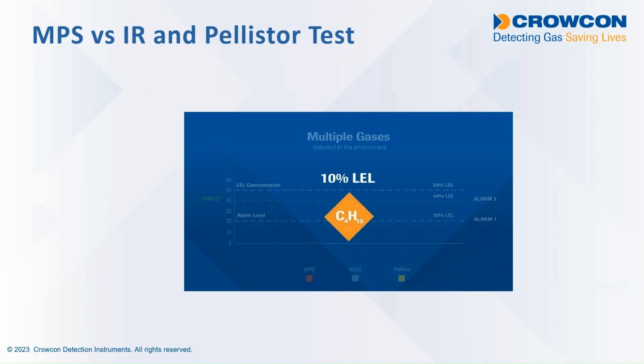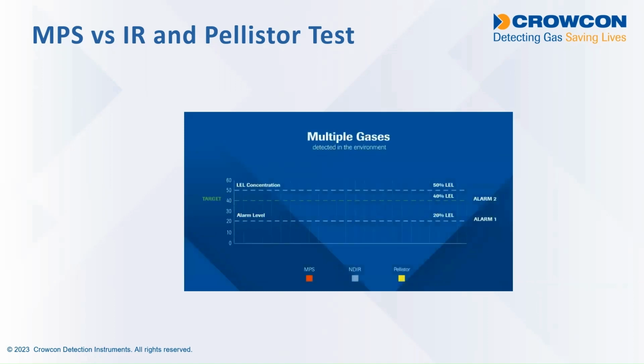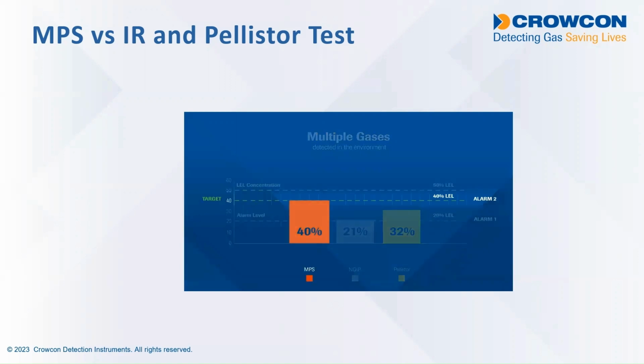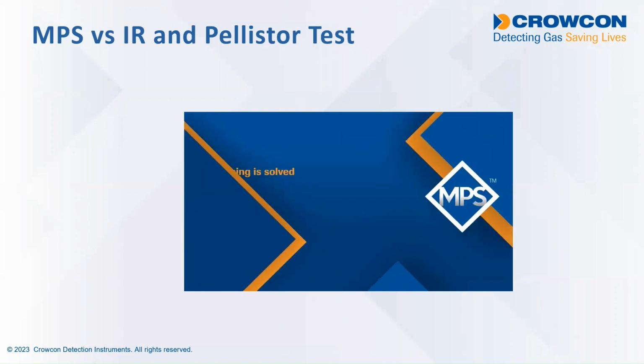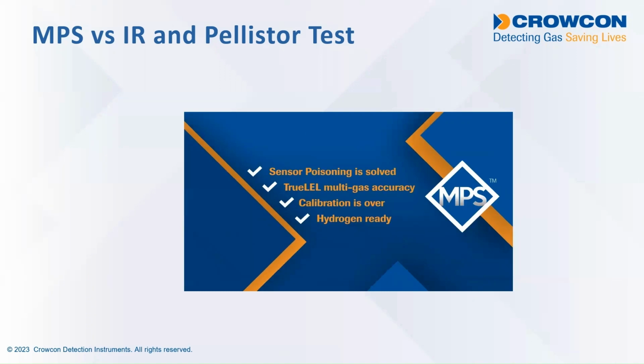And this is exposure to a mix of gases, so 50% LEL of methane, 20% LEL of hydrogen, and 10% LEL of butane. If you have a mixture of gases, the response from the IR sensor and the Pellistor are relatively low, whereas the MPS sensor still reports over a second level alarm at 40% LEL. And that's because it's measuring those different gases accurately. So the MPS sensor isn't vulnerable to poisoning, it gives true LEL accuracy, its calibration is guaranteed for 5 years, and it detects hydrogen.